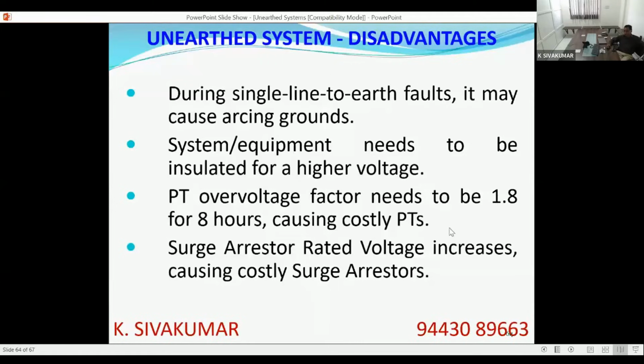If you want to avoid these damages due to overvoltages or higher voltages, you generally have to design the insulation for line voltage and not for phase voltage, because during an earth fault the healthy phases will see the line voltage. So generally you have to design your system for line voltage. That is why they say cables for unearthed systems and cables for earthed systems. Cables for unearthed systems are generally costly.